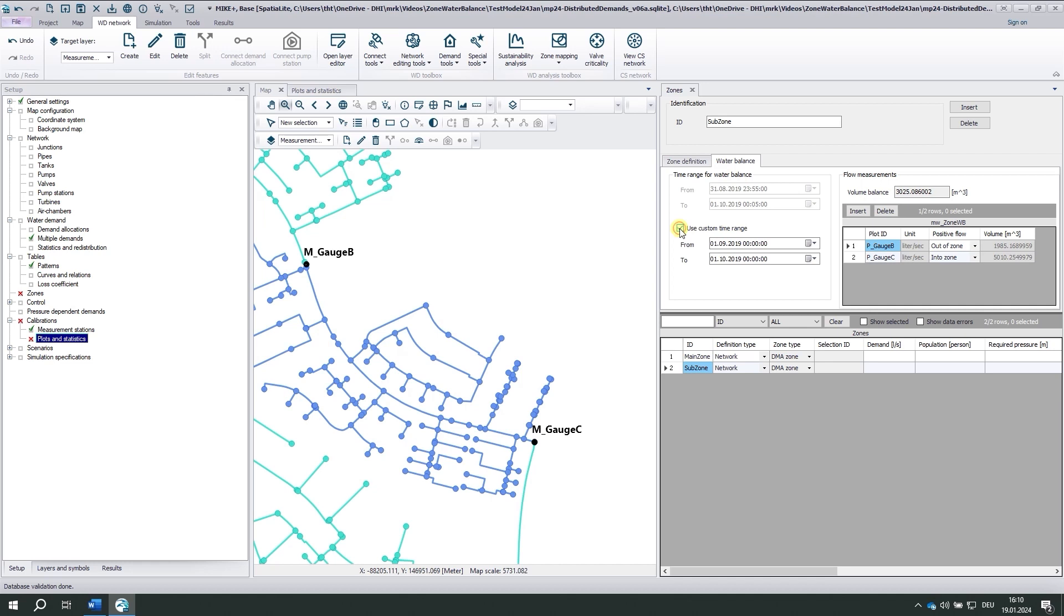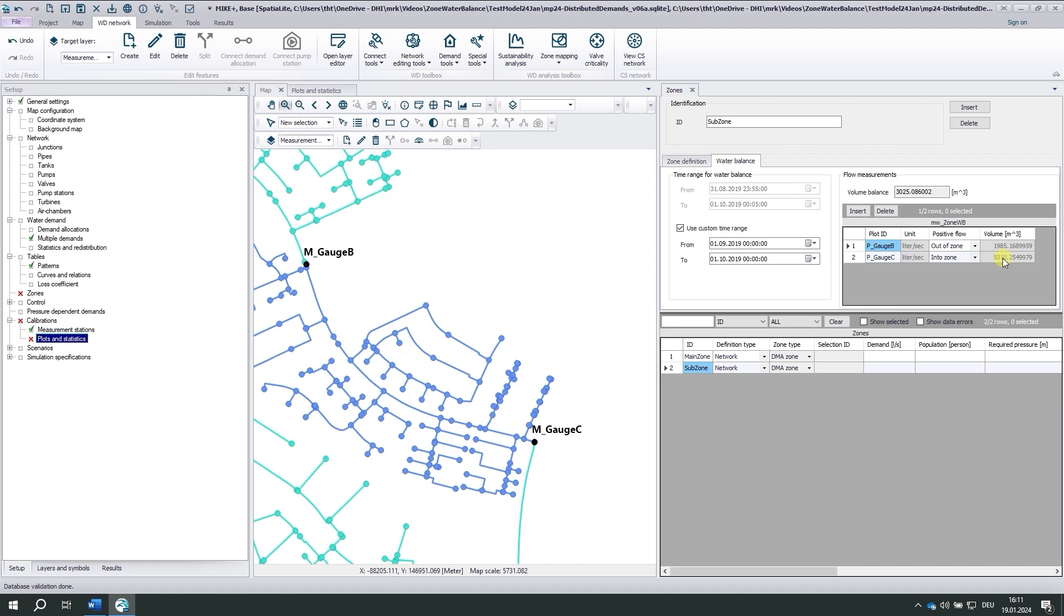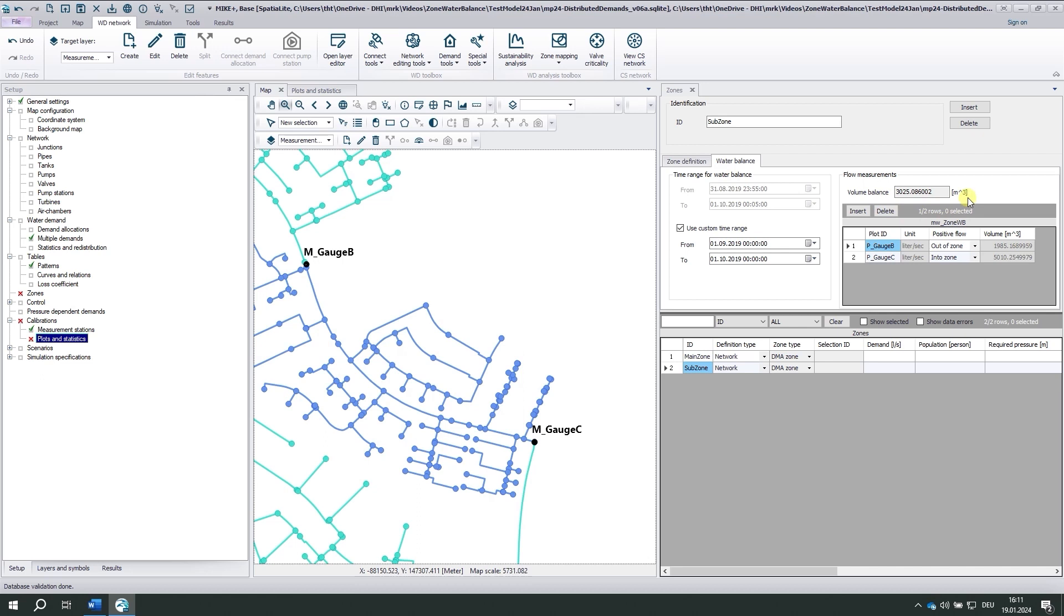The volumes here are computed on the fly. So I see that gauge C delivers 5000 cubic meters within this month. 2000 cubic meters go out of the zone, which equals a consumption of 3000 cubic meters within the zone. And I may check whether these values match my expectations.